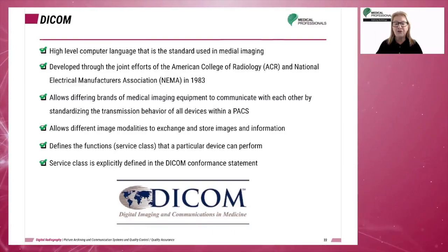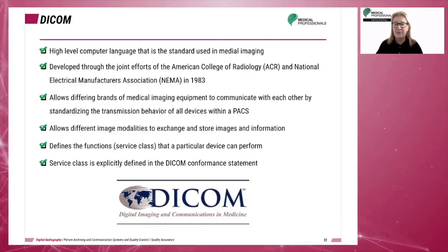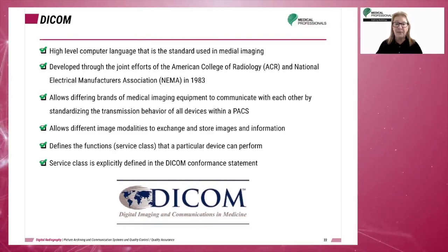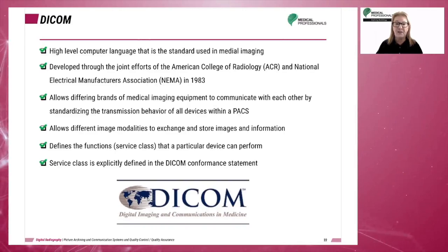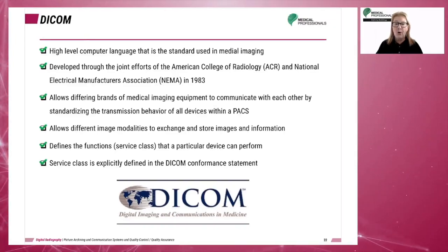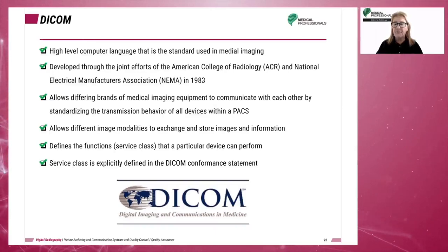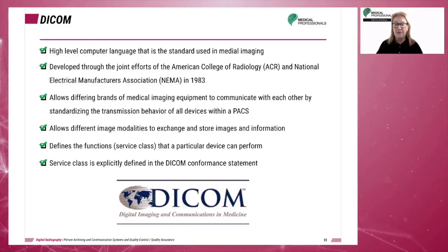DICOM was first introduced in 1985 and became the standard in 1993. DICOM is made up of multiple parts from image display to storage and retrieval. The DICOM standard defines the functions a device can perform as a service class. A device can be a service class user, a service class provider, or both, and the functions a device can perform are spelled out in the device's DICOM conformance statement.